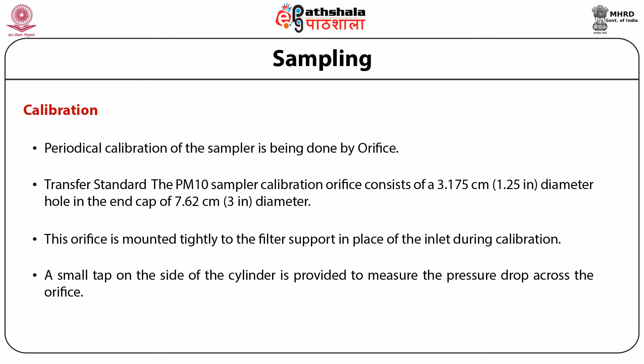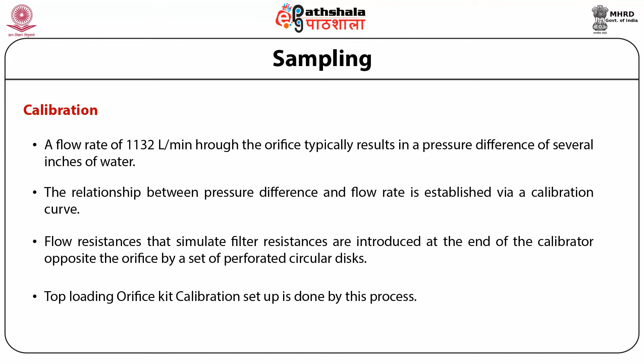At a flow rate of 1132 liters per minute, the orifice typically results in a pressure difference of several inches of water. The relationship between pressure difference and flow rate is established by a calibration curve derived from measurements against a primary standard such as a Roots meter at standard temperature and pressure. Flow resistances that simulate filter resistances are introduced at the end of the calibrator opposite the orifice by a set of perforated circular discs. The top loading orifice kit calibration setup is done by this process.